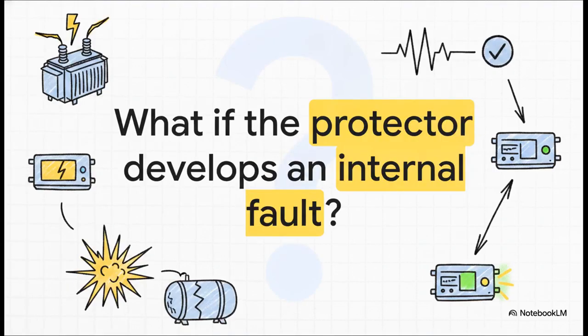Which leaves us with one final, kind of provocative question to wrap up this explainer. What actually happens if the very digital relay meant to protect your transformer develops a silent internal hardware fault of its own? Without built-in self-supervision, how would you even know your protection was broken before it inevitably fails to stop the next tank rupture? Luckily, these relays run continuous diagnostic heartbeat checks, instantly flagging their own faults. Because in power systems, you always have to protect the protector.